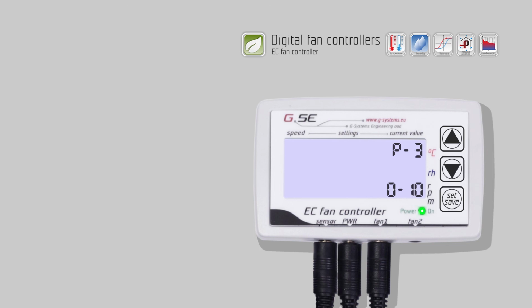In the P3 you can set the EC output signal as 0 to 10 volt, or pulse width modulation. Read the technical data sheet of the fan. The P4 setting lets you choose, when the temperature and humidity are below their set values, should the intake fan stop completely, or should it run on set minimum speed.